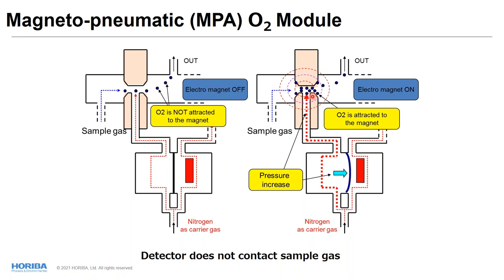Because of this, you can't flow the nitrogen smoothly as you did before. This causes the pressure to increase in this chamber, and there's a membrane right here. The pressure increase bends the membrane, and the degree of bending of the micromembrane is related to the O2 concentration. So we are looking at how much this membrane is bending, and then it is calculated and the reading is shown.